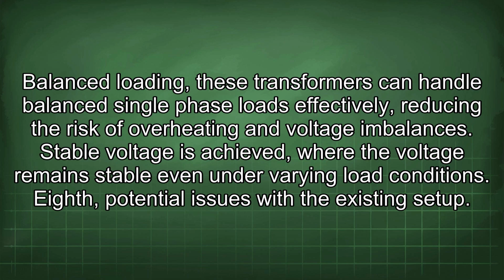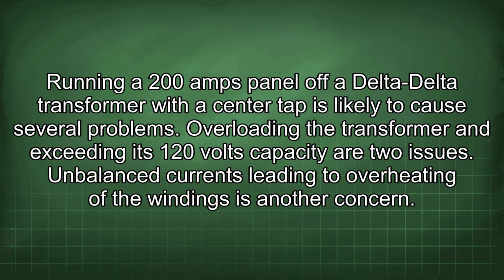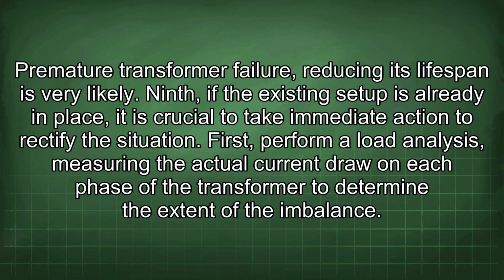Eighth, potential issues with the existing setup. Running a 200 amps panel off a delta-delta transformer with a center tap is likely to cause several problems. Overloading the transformer and exceeding its 120 volts capacity are two issues. Unbalanced currents leading to overheating of the windings is another concern. Premature transformer failure, reducing its lifespan, is very likely.